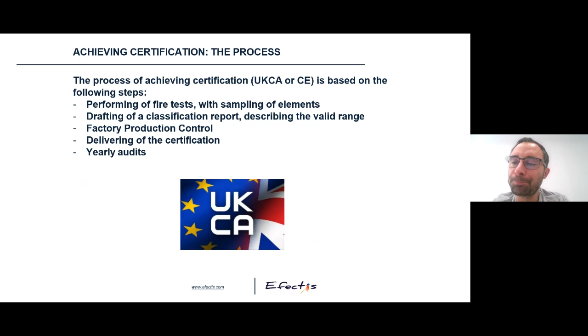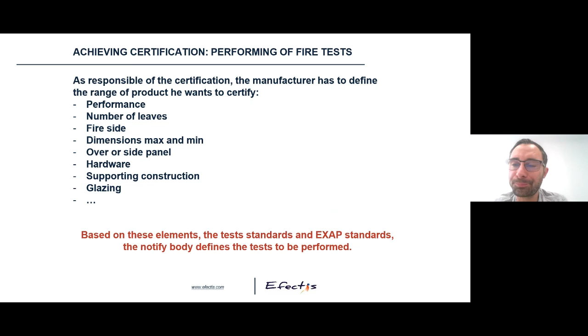As responsible of the certification, when we perform the fire test, the manufacturer has to define the range of product he wants to certify. When we speak about range of product, there are several points to check, such as the performance, for example, the number of leaves, the fire side, the supporting construction, maximum and minimal dimension. So a very exhaustive list of elements that can be put in the range. And based on these elements, the test standard and the EXAP standard, the notified body will define the test to be performed.